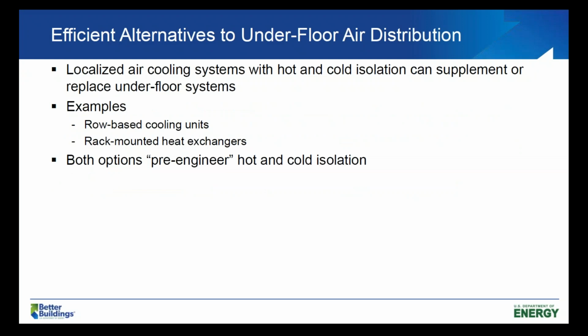All right, so there are other methods than underfloor air distribution for getting cooling air to the system. Those include row-based cooling units and rack-mounted heat exchangers. These are basically moving the cooling closer to the IT equipment, making a closer coupled system, which improves the isolation and thereby the cooling system performance. Next slide.